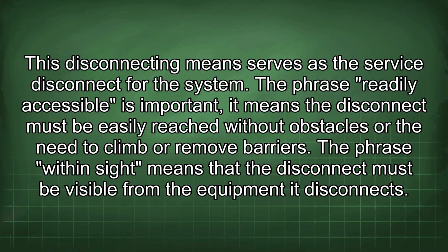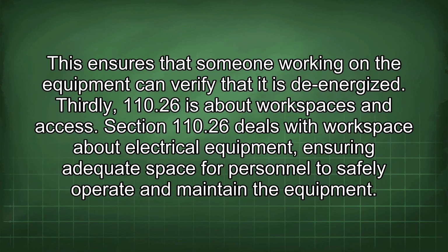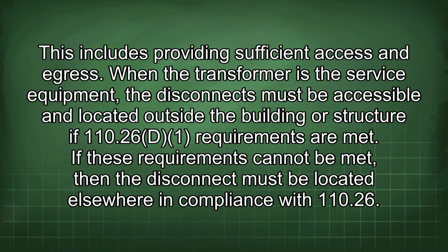The phrase readily accessible is important. It means the disconnect must be easily reached without obstacles or the need to climb or remove barriers. The phrase within sight means that the disconnect must be visible from the equipment it disconnects. This ensures that someone working on the equipment can verify that it is de-energized. Thirdly, 110.26 is about workspaces and access. Section 110.26 deals with workspace about electrical equipment, ensuring adequate space for personnel to safely operate and maintain the equipment. This includes providing sufficient access and egress. When the transformer is the service equipment, the disconnects must be accessible and located outside the building or structure if 110.26(D) requirements are met.